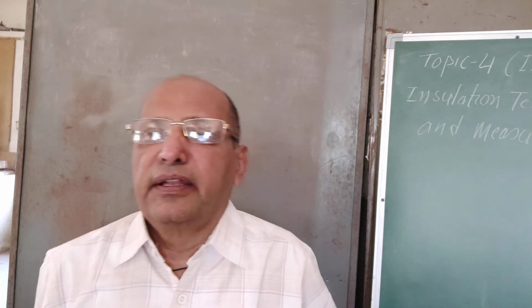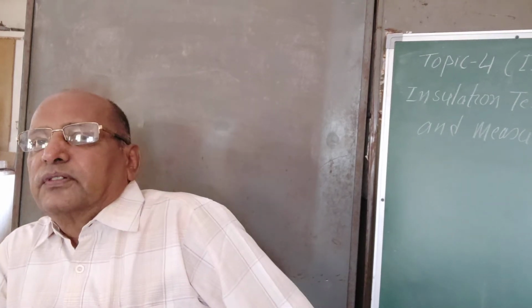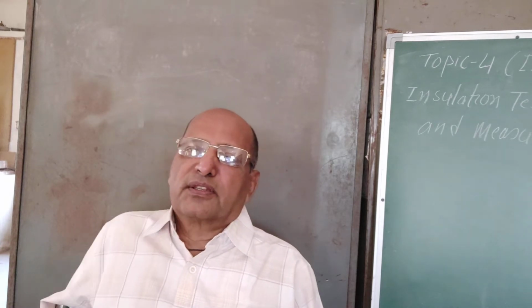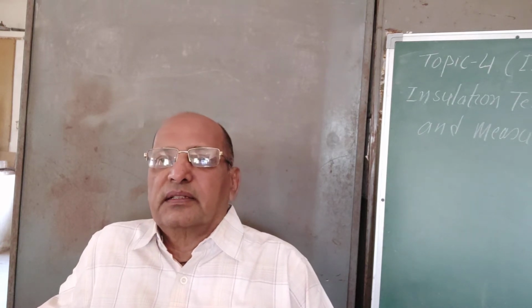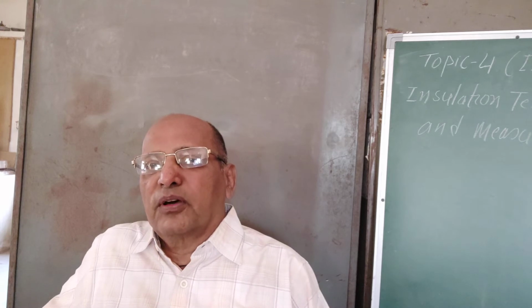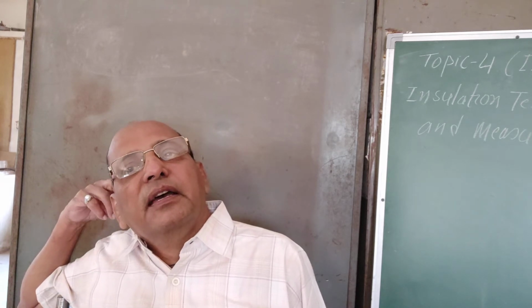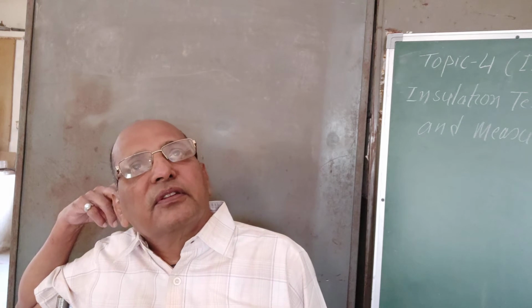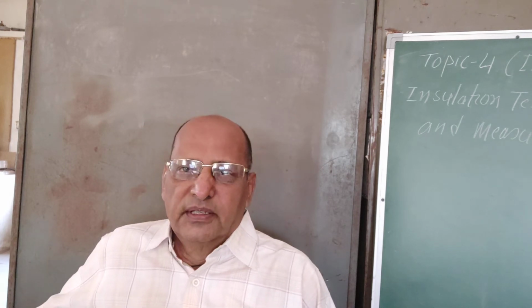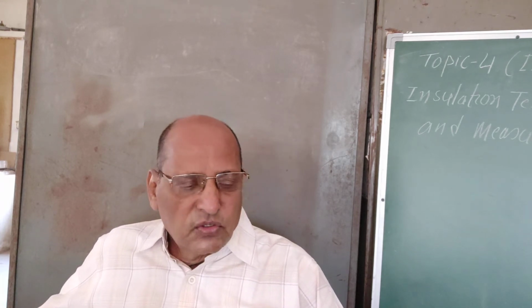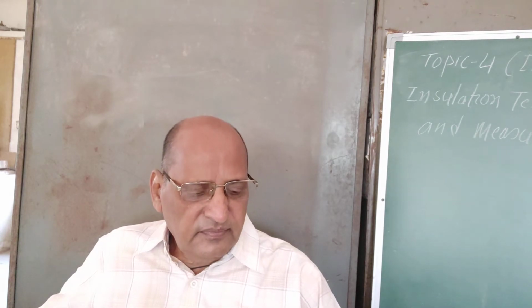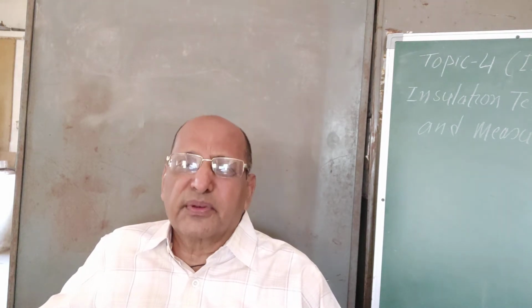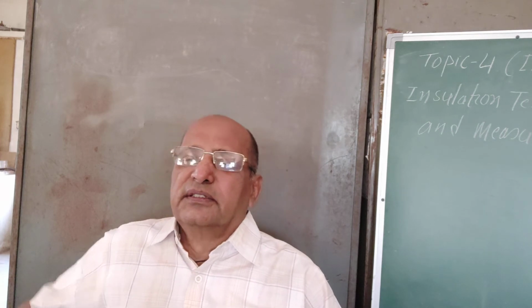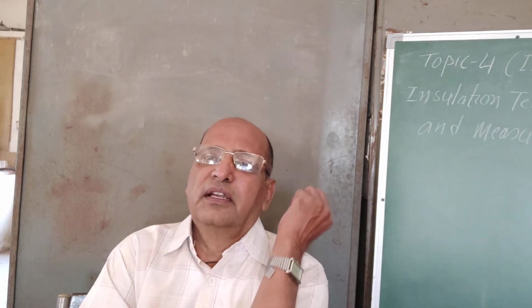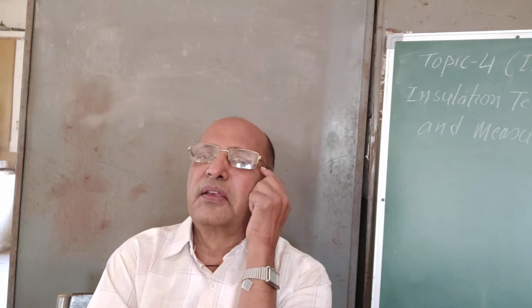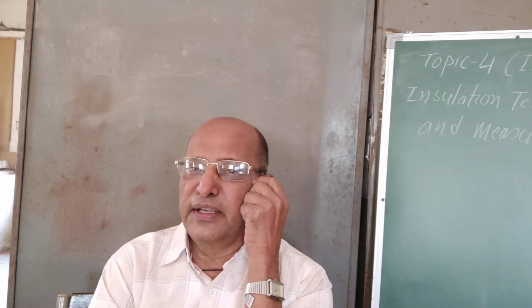The internal temperature of the winding is to be measured in the case of a transformer. Normally, for a distribution transformer up to 500 kVA, there is a temperature gauge fitted on the transformer itself, which shows the temperature. Near the conservator tank, this temperature indicator is installed, and we can read the temperature, so that will give the temperature of the winding.